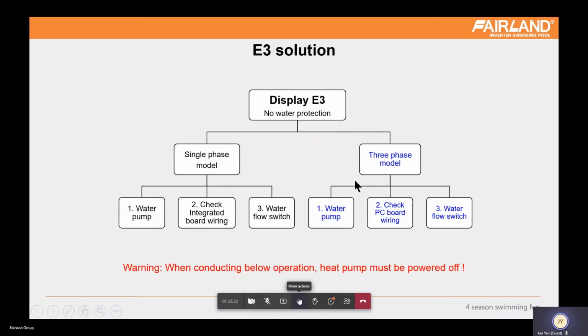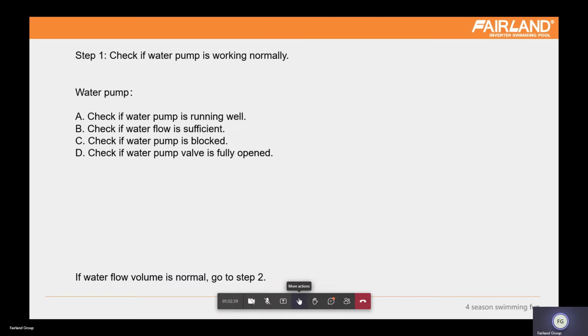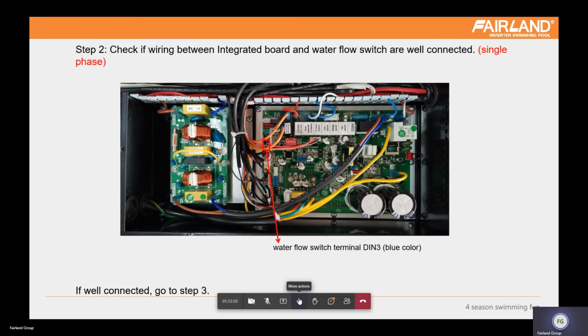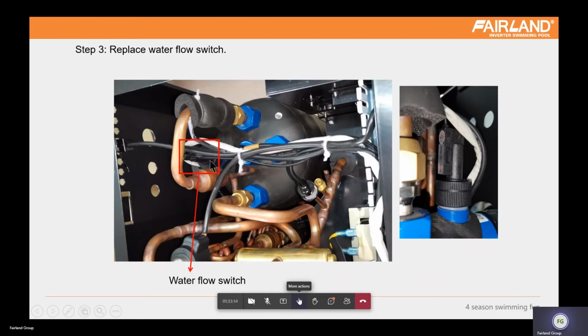E3 is no water flow protection. Normally we will check the water flow volume to see if it is normal, the same method to check it. Check the water pump, if the flow is sufficient, if the water pump is blocked, and if the bypass valve is fully open. If that doesn't work, we will check the wire between the water flow switch at terminal DIN3 and the integrated board. If it is well connected, we will replace the water flow switch, which is installed on the top position of the heat exchanger.